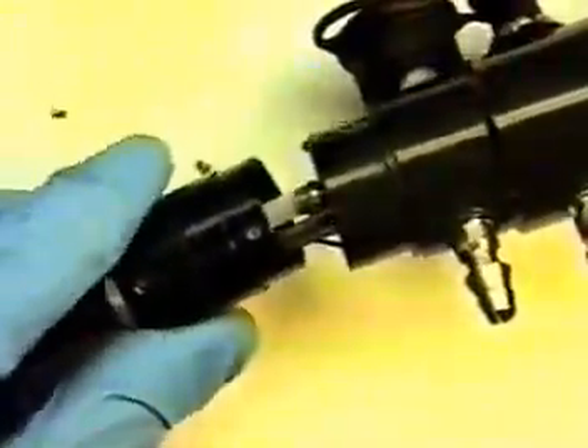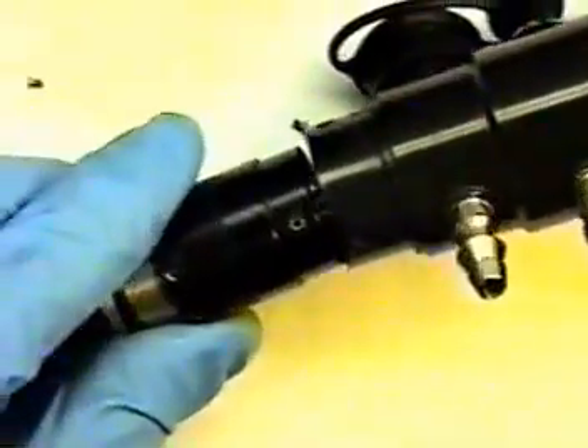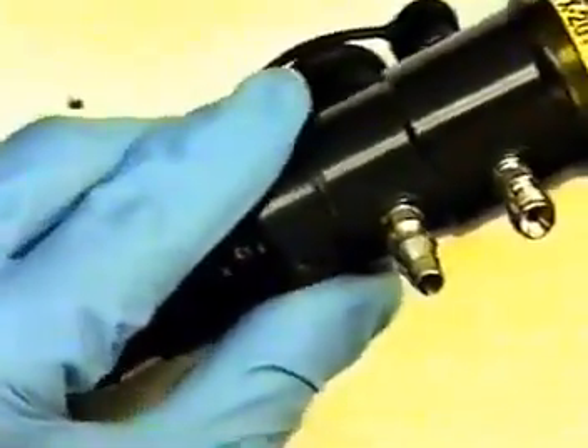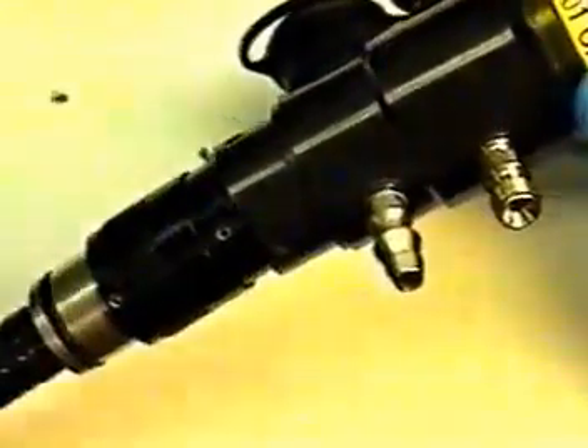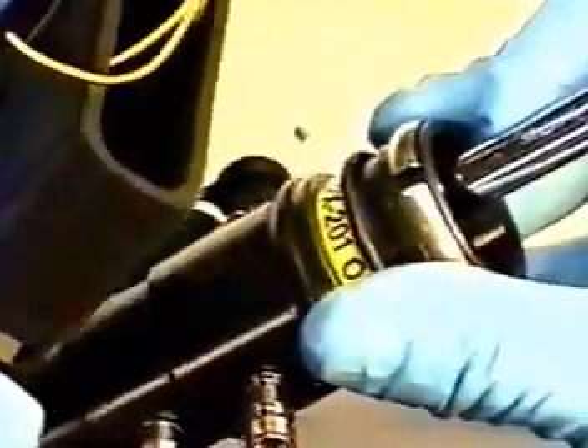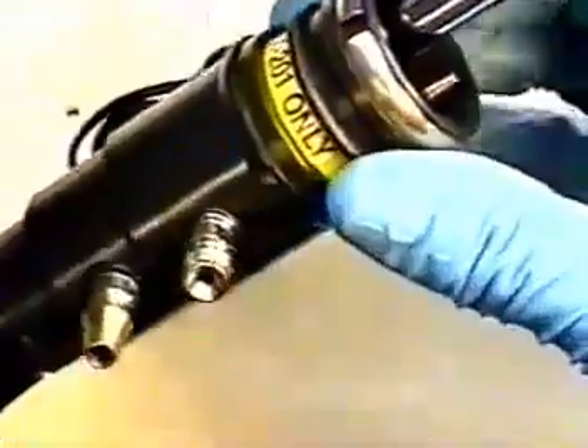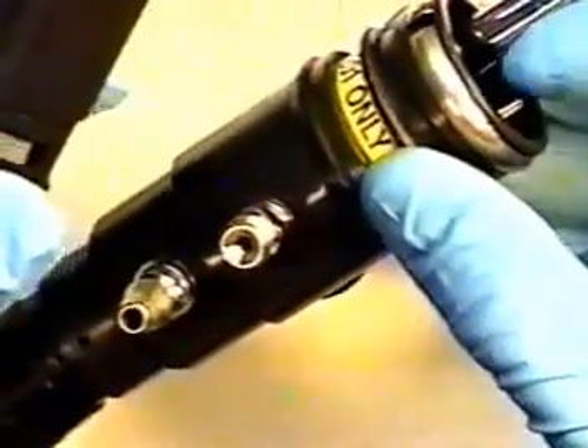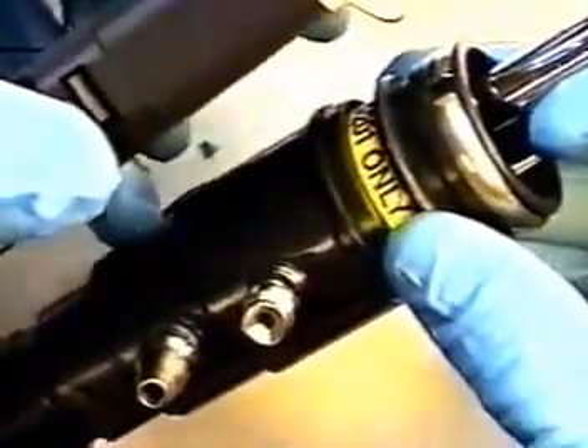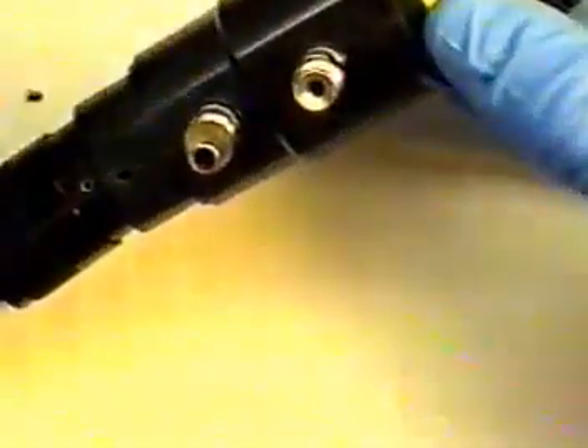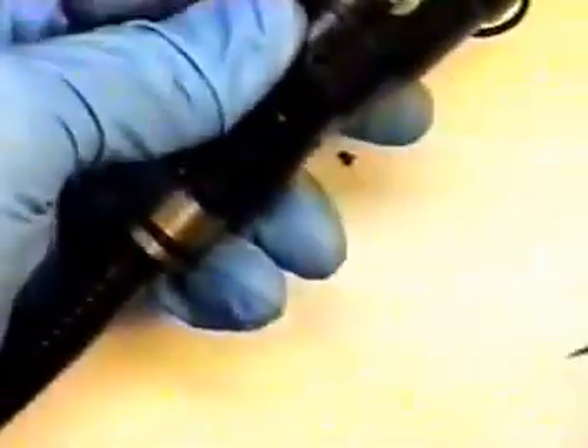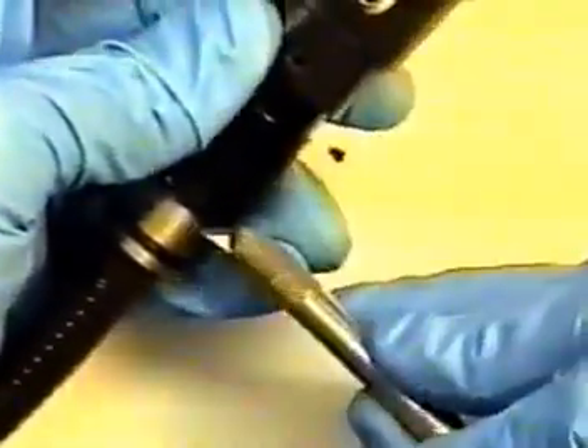Once the suction channel is on properly with our clamp tightened down, we can now pull up the body covers to reinstall the light guide probe. The light guide probe, in reference to our video connector, will be up, whereas the top of the probe will be in the up position in reference to our video connector. Also, previously, if you made any reference marks on the instrument, you can match those up.